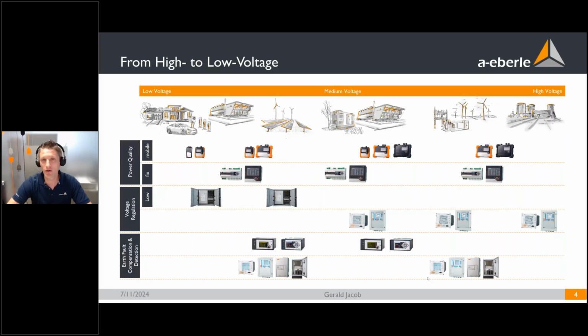As I said, we are active in all voltage levels. Here is a matrix showing where we are located, in which voltage level, with which products, and what kind of different product groups we have. In the first two rows you see power quality, fixed and mobile — two different product groups. The mobile one is for using these devices for a certain time, and power quality fixed, also called PQSys, is for fixed installation in utilities. The second big row is voltage regulation. We offer low voltage regulation systems for 0.4 kV, as well as regulators for big transformers for the middle, high, and highest voltage levels.